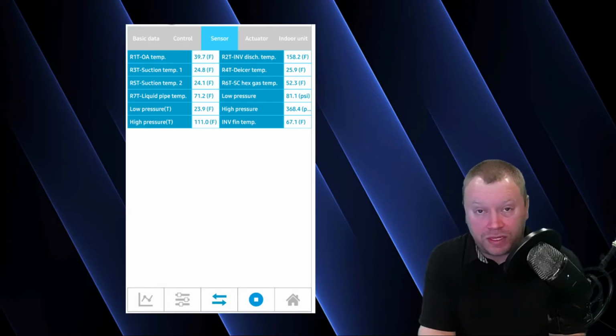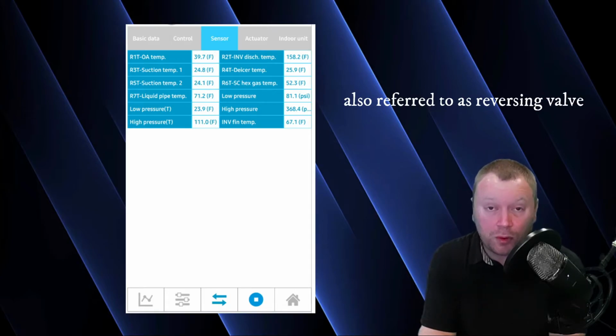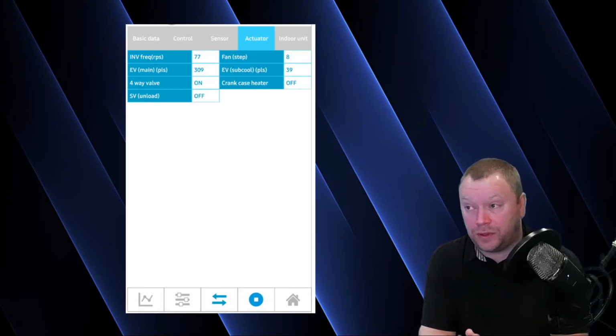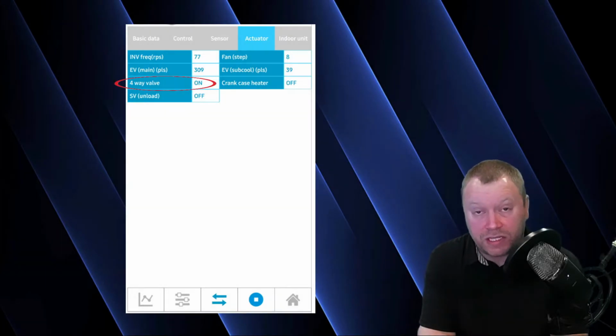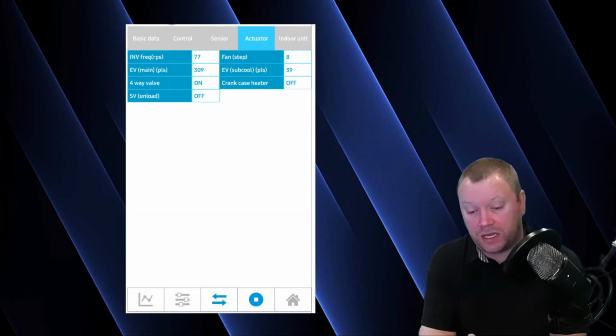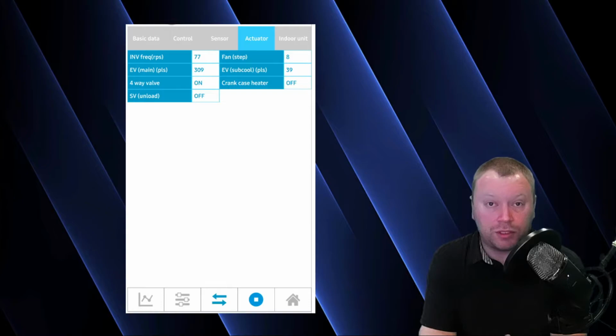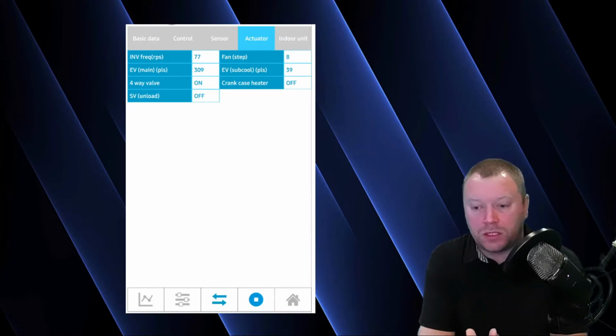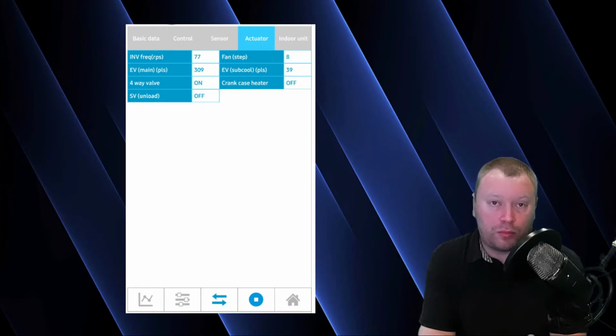Well, the next component in the system is the 4-way valve. The 4-way valve is going to be located in the Actuator tab. So if we look at the Actuator tab, you can see that the 4-way valve position says on. On means energized. In a Daikin mini split or VRV system, all of our 4-way valves energize in the heat mode. If you're in cooling, they de-energize, and therefore when you kill power or lose power, they will always fail to cooling. Which, by the way, speaking of killing power or losing power, you never want to shut the unit off with the disconnect while it's running. It's very bad for the equipment, so always make sure you turn your thermostats off, wait for the compressor to shut down, and then remove power from the system.